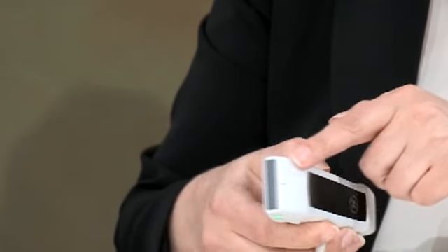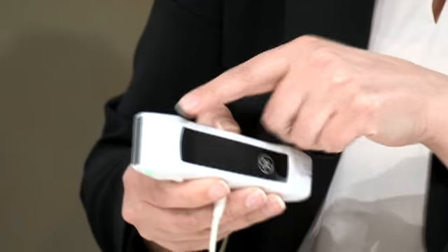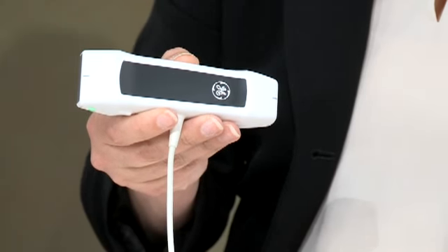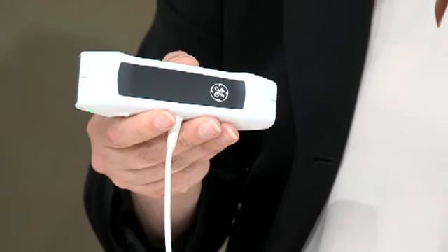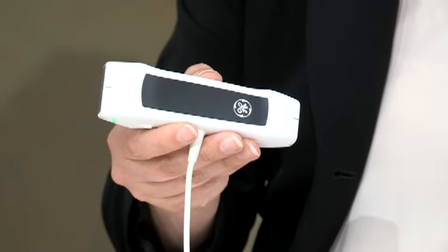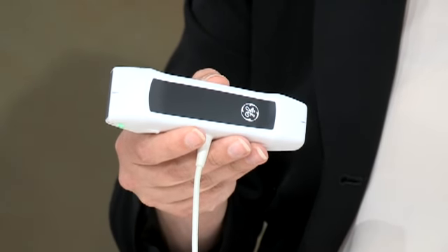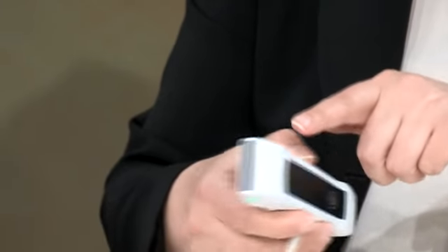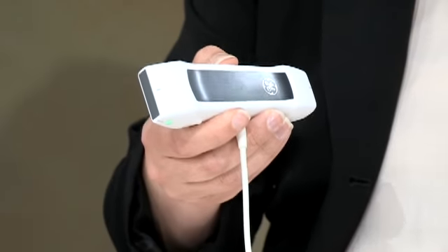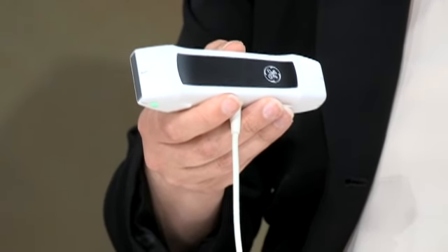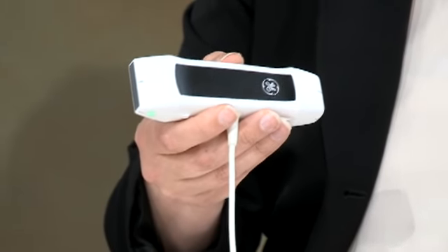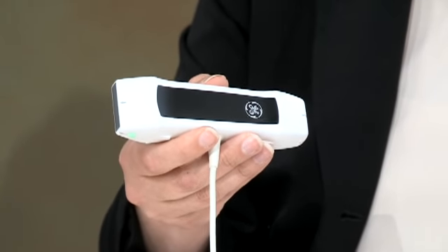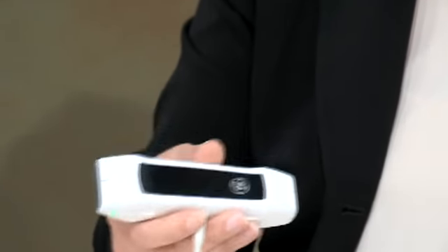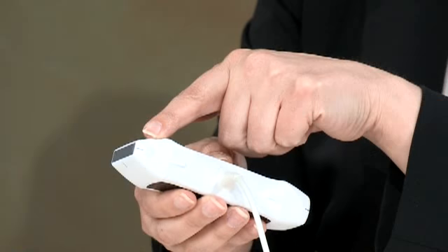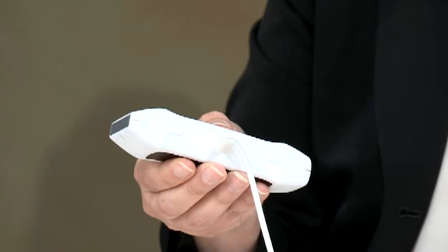The linear or the shallow imaging end of the transducer supports a broad bandwidth frequency range of 4 to 8 megahertz, as well as an imaging depth up to 8 centimeters. You'll see for both the phased and the linear transducers that they're very small apertures that enable imaging in very tight spaces, such as intercostal or behind a leg for a lower extremity evaluation. There's also an LED indicator for both transducers that lets you know which end of the probe is activated.